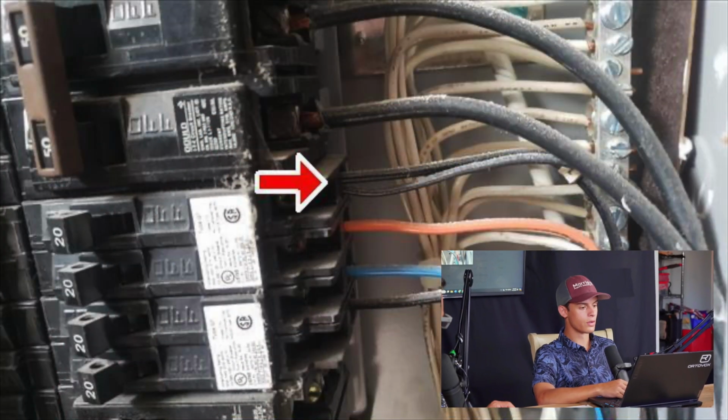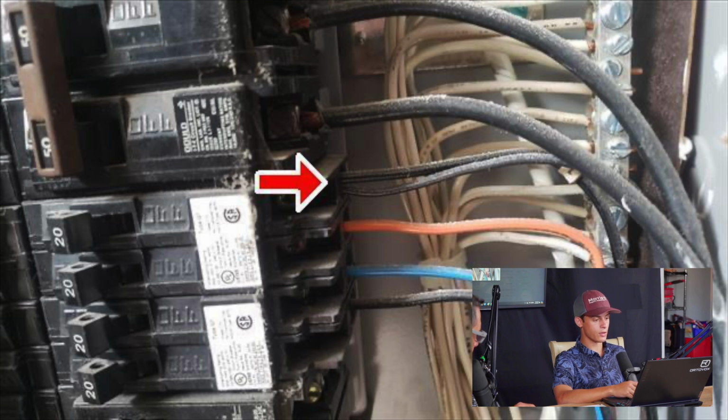And a qualified home inspector is definitely going to be able to do that and then look inside there and actually determine how the wiring connects to the breakers. And this is a condition we find quite a bit. What's going on here, Wood? So this looks like they ran out of room for more breakers, or they just got lazy, and they just put 2 wires into 1 breaker, which is not acceptable.